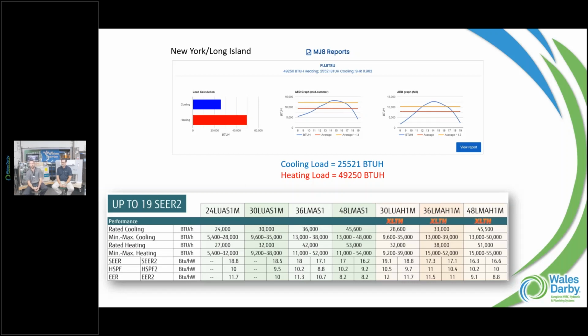So knowing what we have available to us, again, everything's going to go back to that design and technical manual. That could be a balance point in which we size for the two seasons, and then we need to play nice with a dual fuel approach. Maybe there's an existing boiler, or another piece of equipment in the house that we can switch over to, and not buy a larger piece of equipment just to carry all the BTU load we think we need, and then suffer on the summer side. Because then it's way too large, it short cycles, humidity is a factor - and that's where I think you were sitting with this past issue.